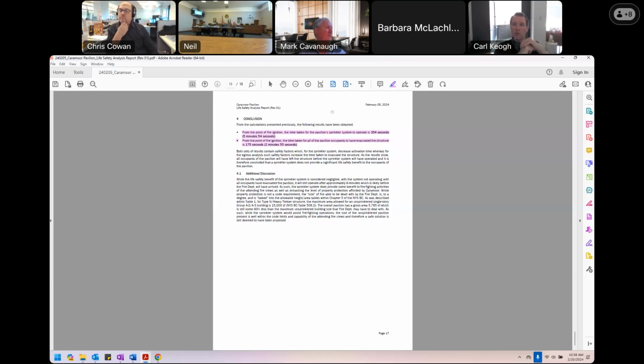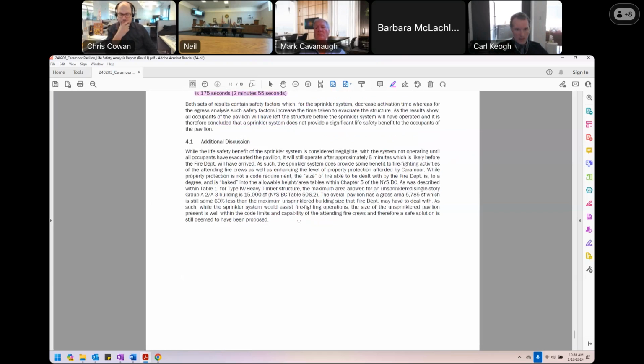However, even though we exceeded the 5,000 square feet relative to the occupancy type, we are still well within the maximum permitted building area for a heavy timber structure without sprinklers per the Chapter 5 provisions. In fact, you would be allowed a heavy timber structure with those occupancy groups of up to 15,000 square feet without sprinklers, and we're at 5,785. So we're still well within the maximum parameter of an unsprinklered fire that the fire department could cater for. Whilst it would be a benefit to them, we're still well within the overall limits for Chapter 5 for height and area allowances.